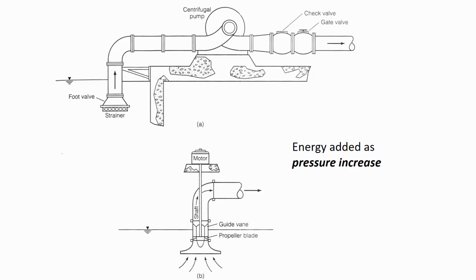If we need to pump water from, say, an aquifer that may be hundreds of feet underground, we can just have a rotating shaft that goes down to wherever the water surface is, and then the impeller is down there. We don't have to put the pump all the way down, and we couldn't have the impeller all the way up, because if the impeller was at the surface, the water would cavitate before it was able to be lifted that high. Depending on where your municipality gets its water, if it's groundwater, they may have pump houses throughout the city. Usually you'll see a big motor mount at the surface, but you may not always see the pump itself because the pump itself may be buried.